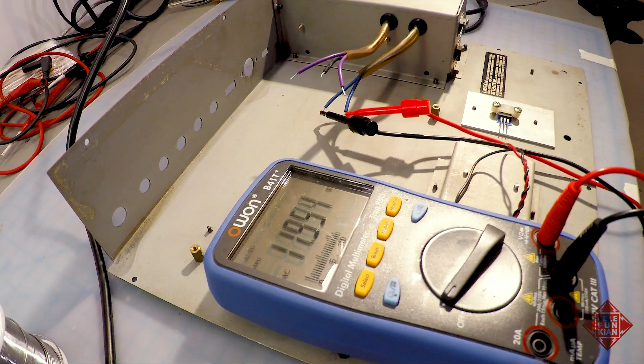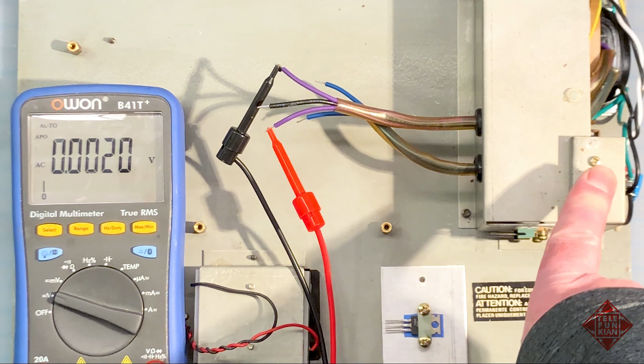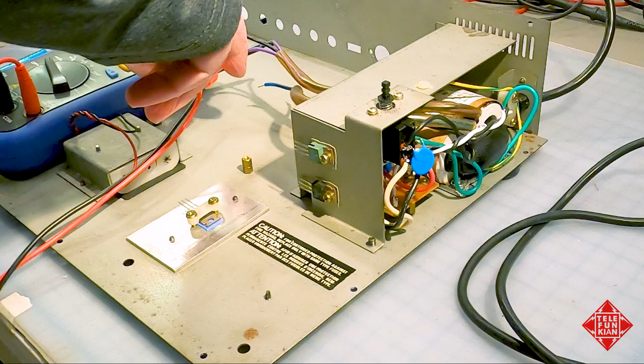We'll turn that off and come over to the other windings. Here we should see roughly 30 volts from side to side. It'll probably be a bit higher than that unloaded, maybe as high as 36 or so. Oh, even higher than that, so about 40. And if we measure from the center tap, we've got about half that.